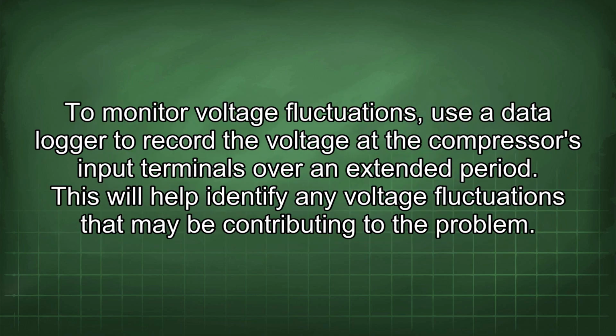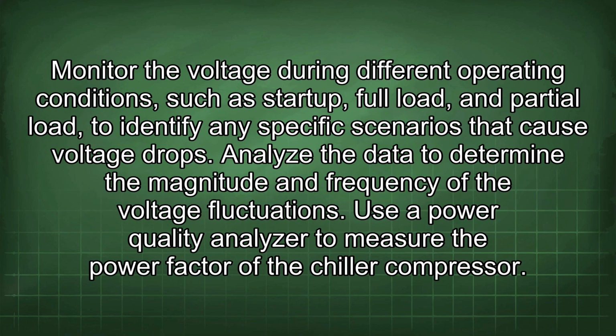To monitor voltage fluctuations, use a data logger to record the voltage at the compressor's input terminals over an extended period. This will help identify any voltage fluctuations that may be contributing to the problem. Monitor the voltage during different operating conditions, such as startup, full load, and partial load, to identify any specific scenarios that cause voltage drops. Analyze the data to determine the magnitude and frequency of the voltage fluctuations.